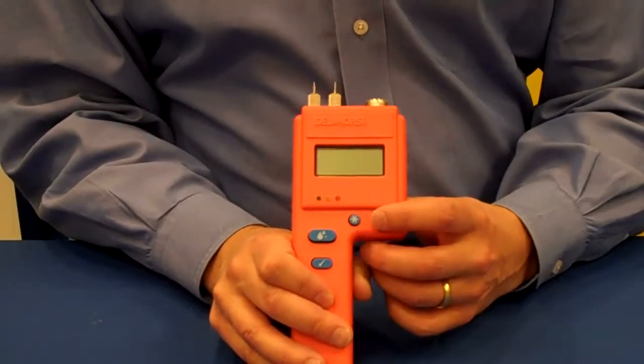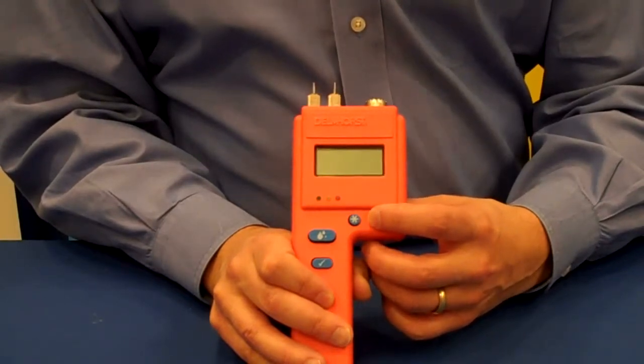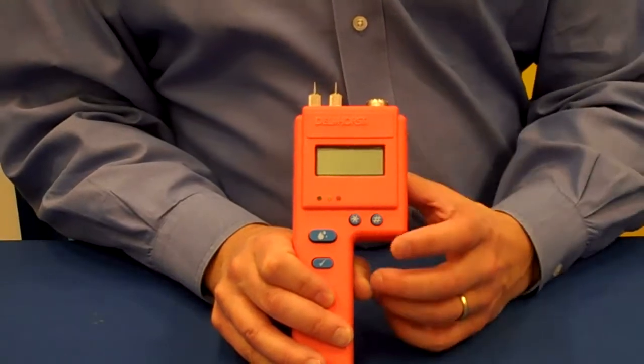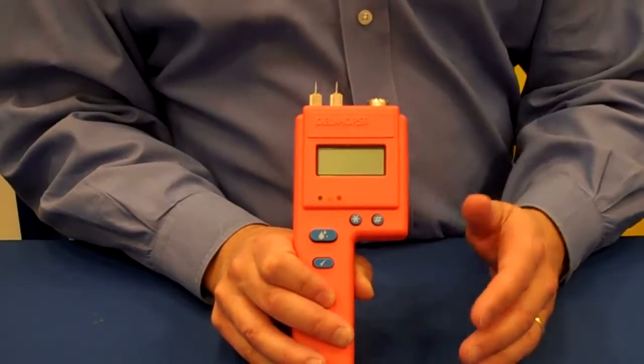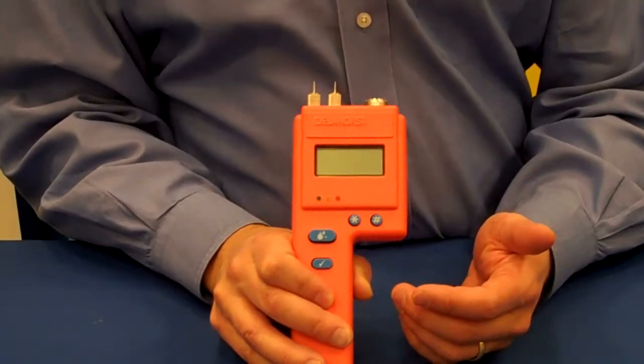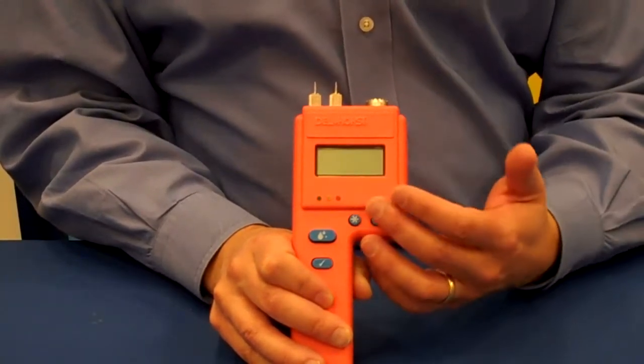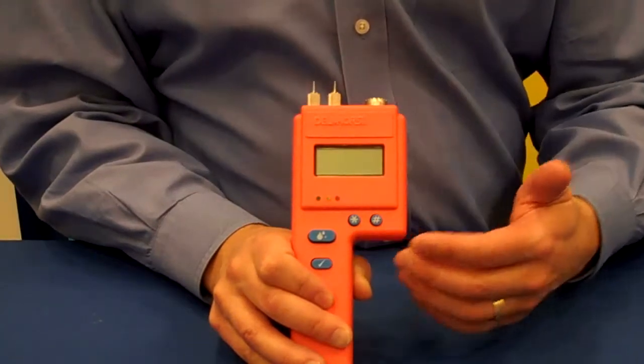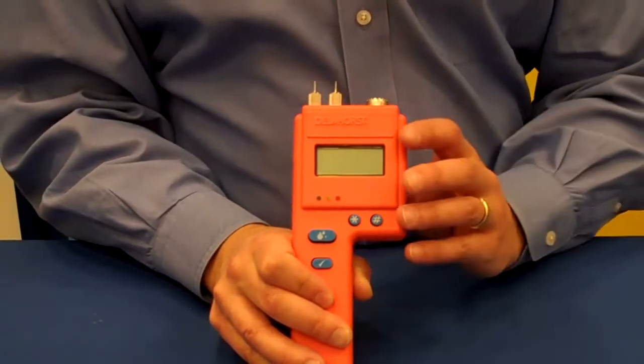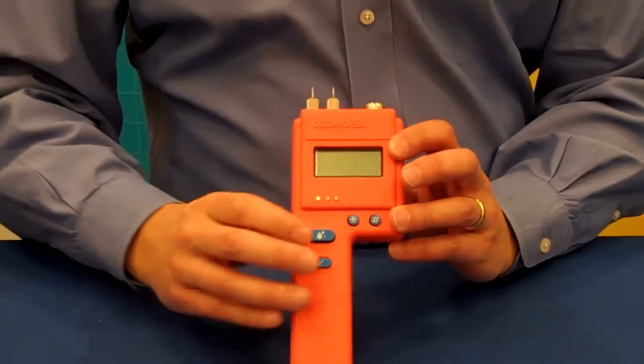The meter also offers an adjustable alarm setting for each scale. The alarm is a great feature because it allows you to identify a dry standard, set the alarm for that value, and then as you're taking readings, you listen for the alarm to go off, indicating that you're at a higher moisture level than the dry standard.